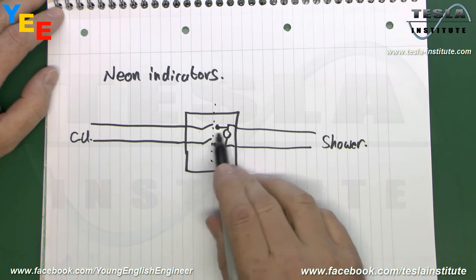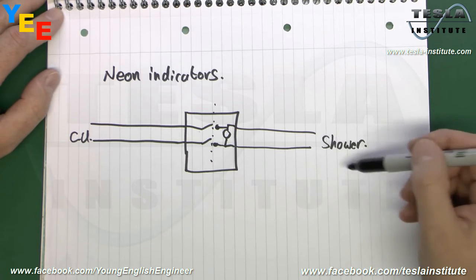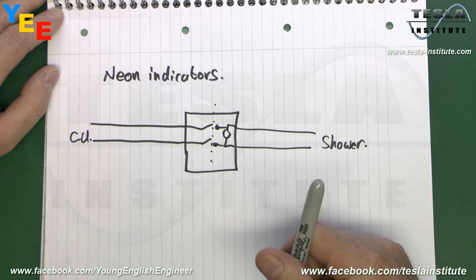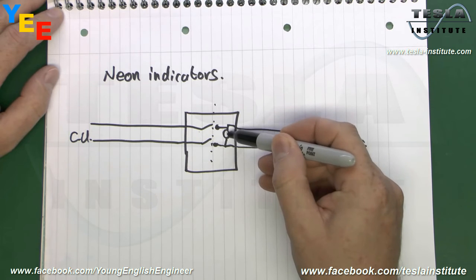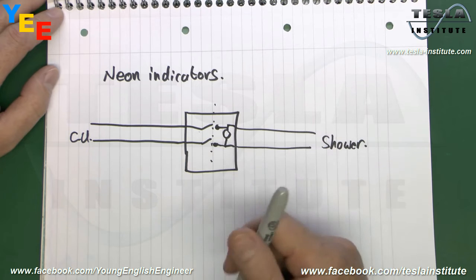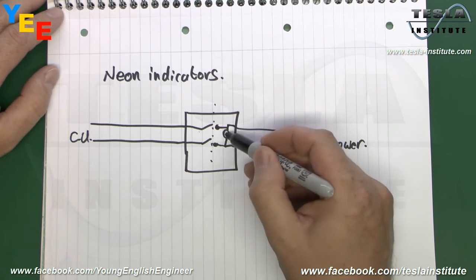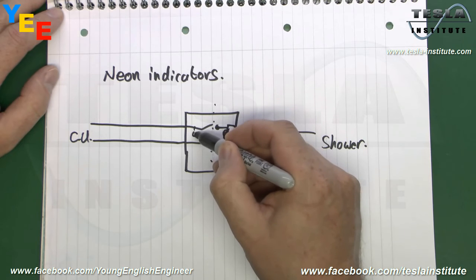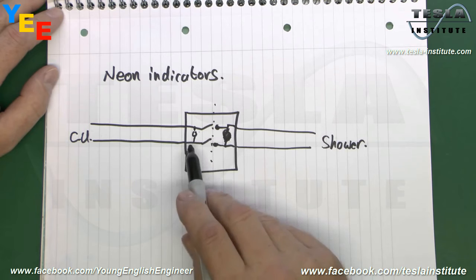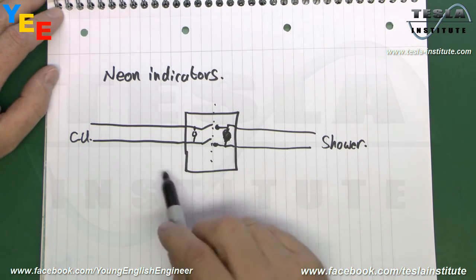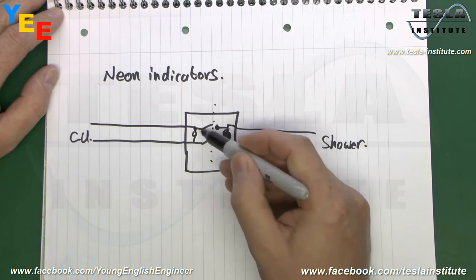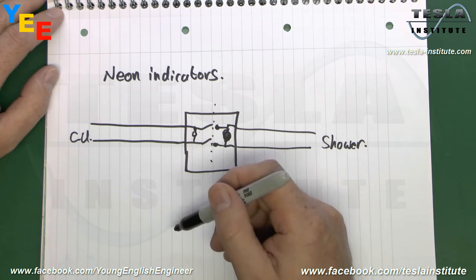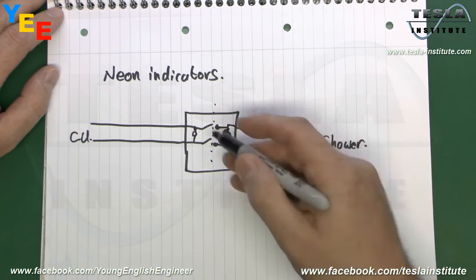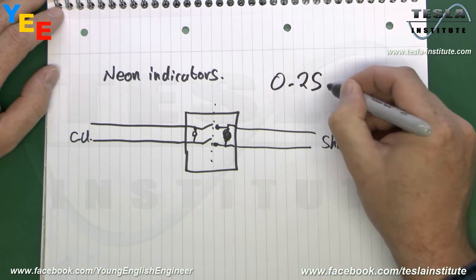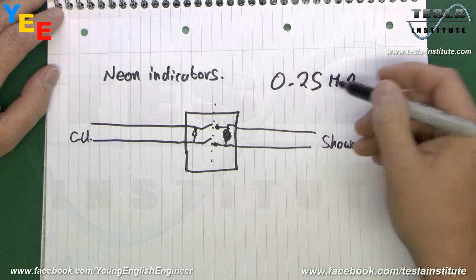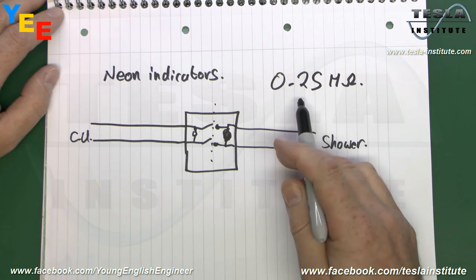But if you inadvertently left the switch in the on position, not only are you going to be testing whatever load is on the end of this, which again is not ideal, as shoving, say, 500 volts into things may cause them to be damaged, but you're actually also going to be testing this little neon indicator, and it's not unknown for these switches to be put in backwards. So instead of the neon ending up here, it ends up over here, and the result is that when it's on, the neon stays on all the time regardless of the position of the switch. But if you then test this, you're actually testing across this little neon, and if you put 500 volts across a neon, it will show up as a fault, and typically in that circumstance you'll get an insulation resistance reading of around 0.25 megohms, which clearly is far below the amount required, but it's still considerably more than a short circuit.